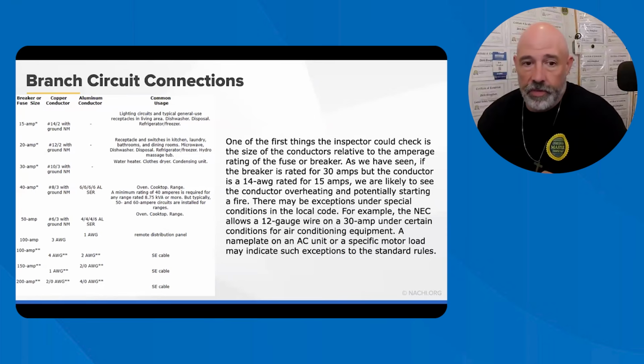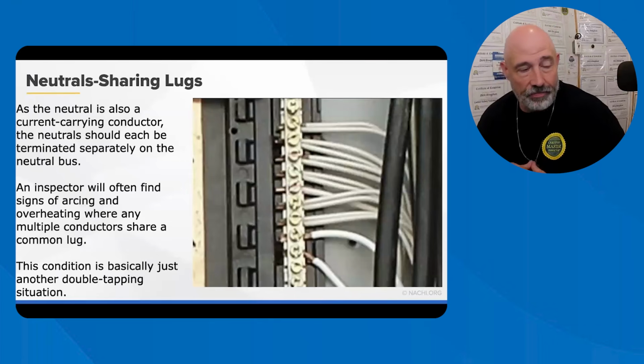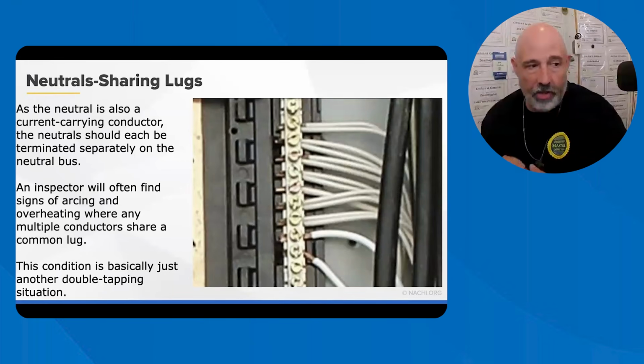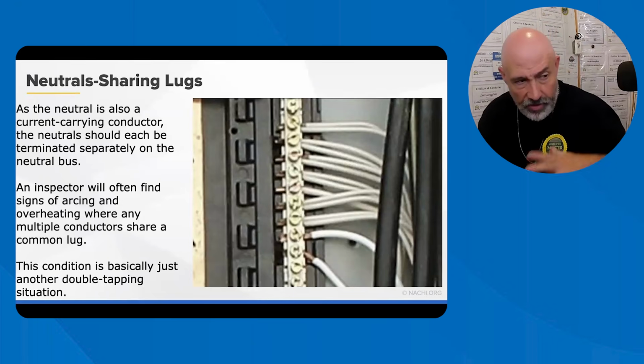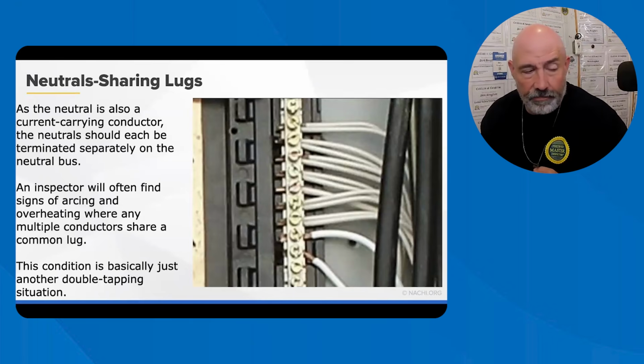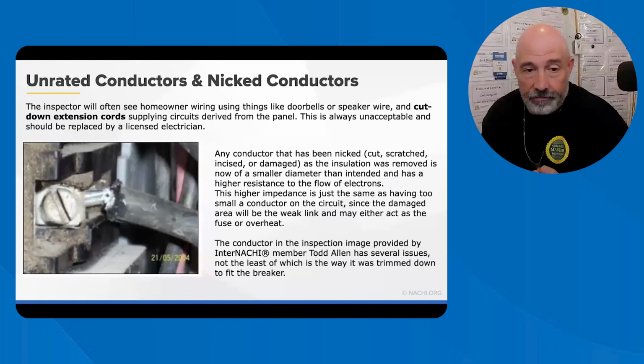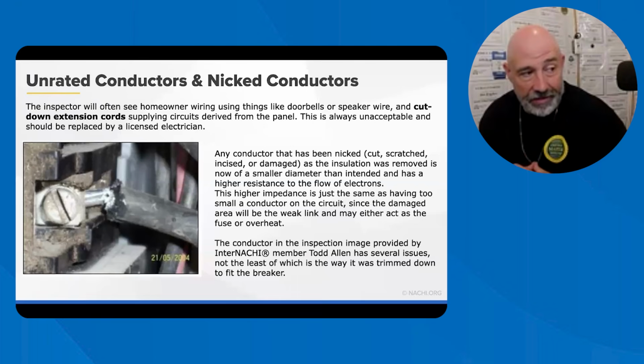So there you go. I'm not going to go too deep into this, because of neutral sharing lugs. If the panel board says that you can, you want the same gauge wire in those when they are sharing that lug. So two 14 gauge wires are perfectly fine if the manufacturer says so. But if you do a 14 gauge and a 12 gauge, you might have some issues there. So make sure you're looking at this stuff and are vigilant about it. And if you see any scarring or scorched wires or anything like that, take notice of that kind of stuff.